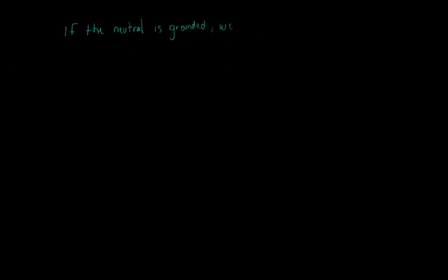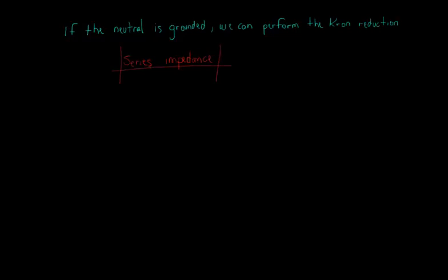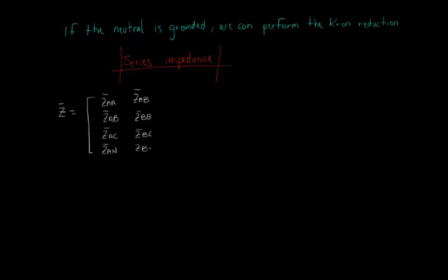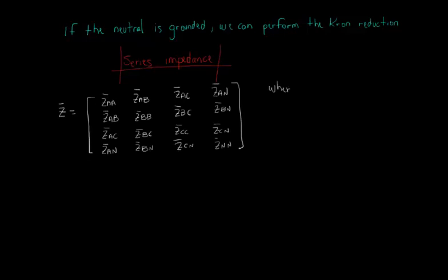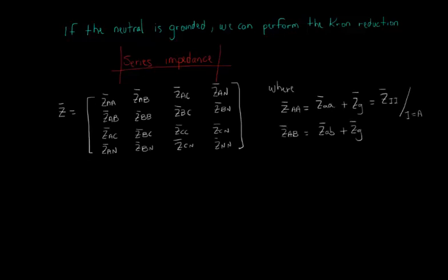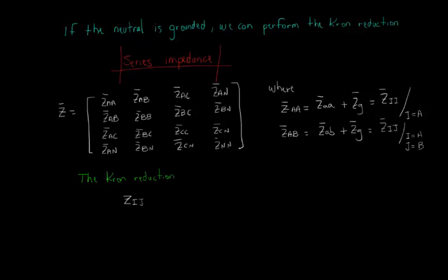Now, let's assume that the neutral is grounded in both terminals. As we saw, in a 3-phase 4-wire line, we have a 4x4 series impedance matrix where each element is affected by Carson's equations represented by ZG. With the neutral grounded in both terminals, we can perform the Kron reduction in which the 4x4 matrix is reduced to a 3x3 matrix. The elements of the reduced matrix are calculated according to the following expression.